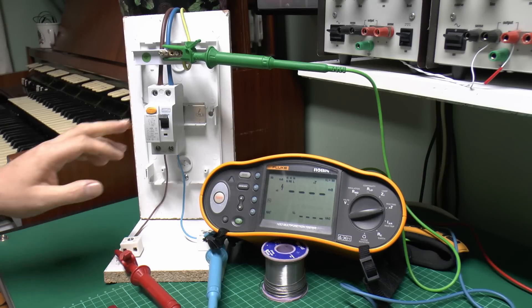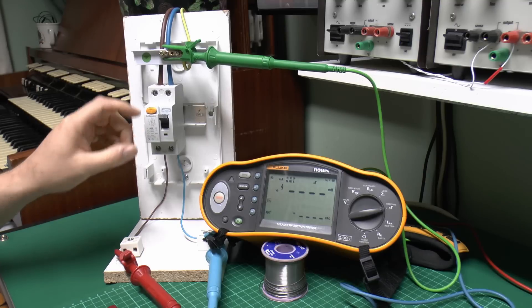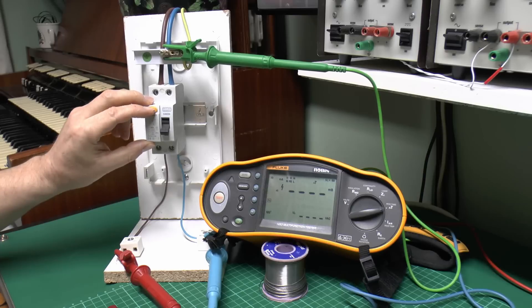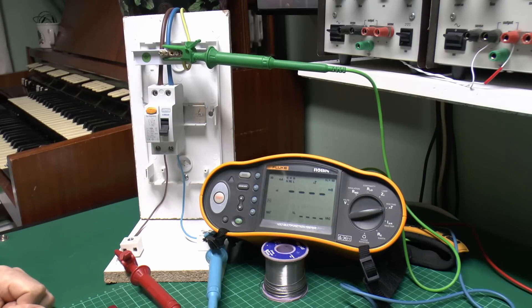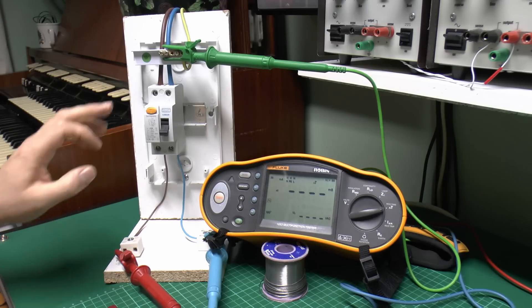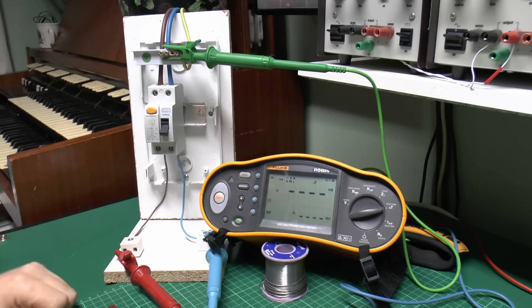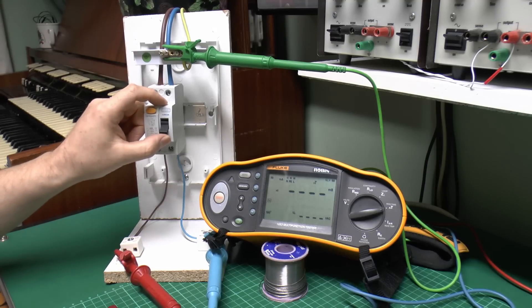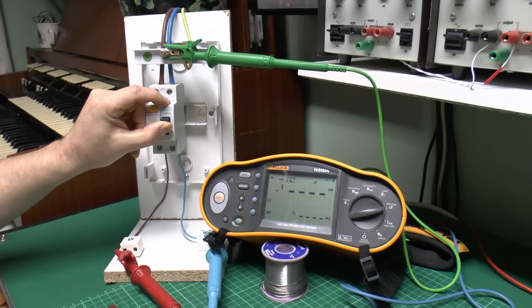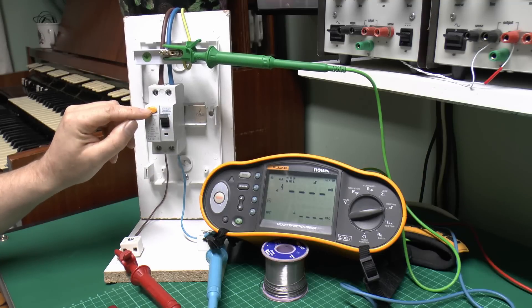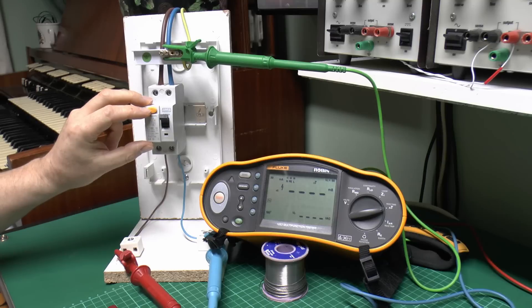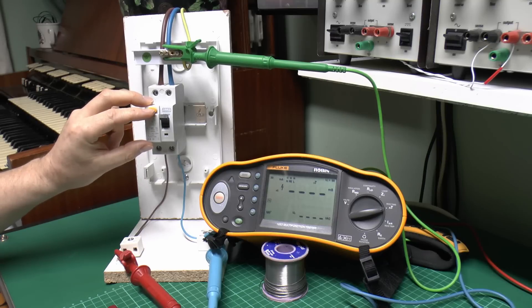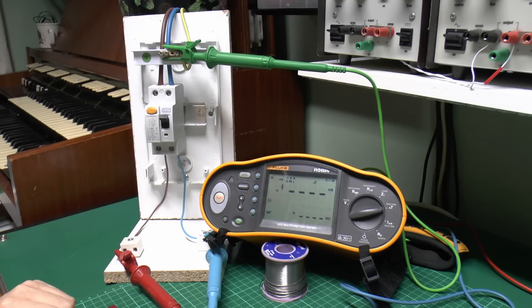Now I'm wondering why it's got this test button on here, and all that does is basically trip the device like that, basically to confirm that it does actually still work internally. Unfortunately, that doesn't really tell you anything about the state of its operation, because it doesn't tell you how long it's taken to trip, or in fact what the test current was. It's purely there so that the end user can do a very basic check just to make sure that the thing does actually work. And if you press the button and it doesn't switch off, then of course the device should be replaced.